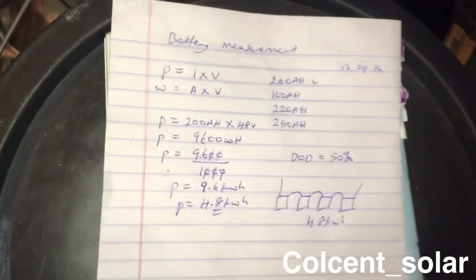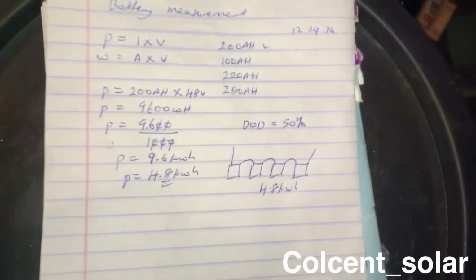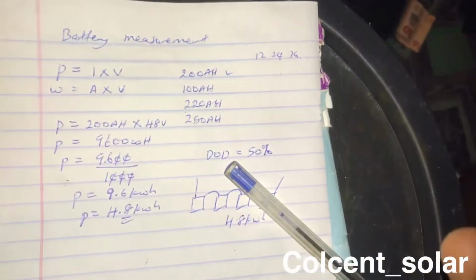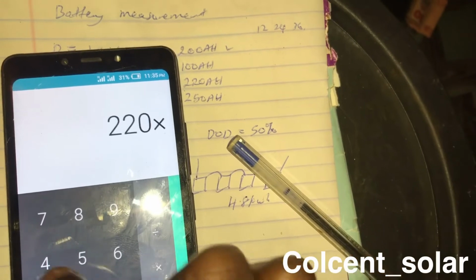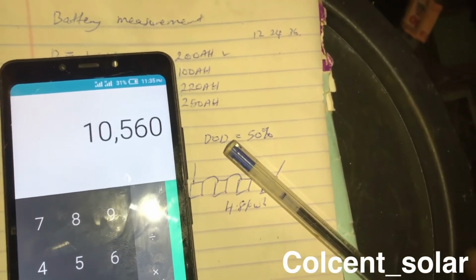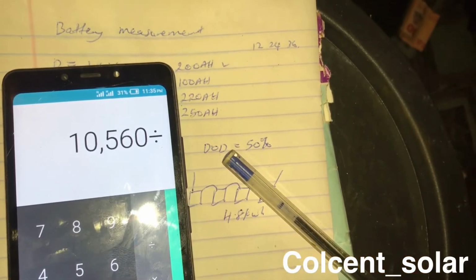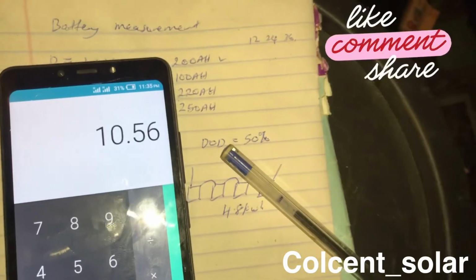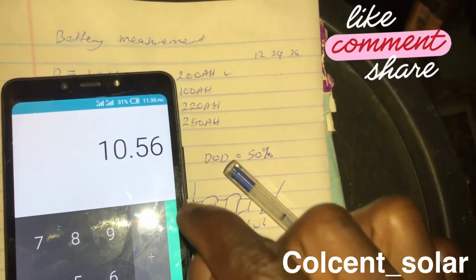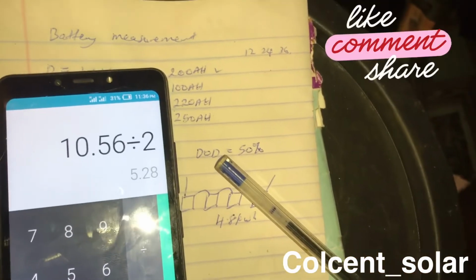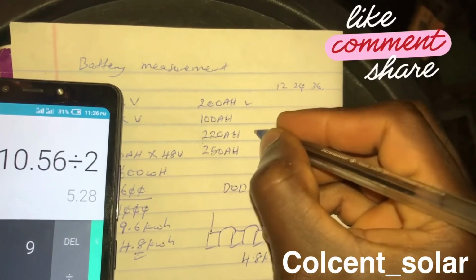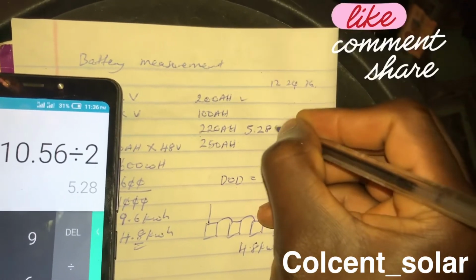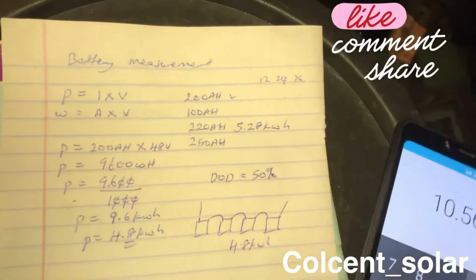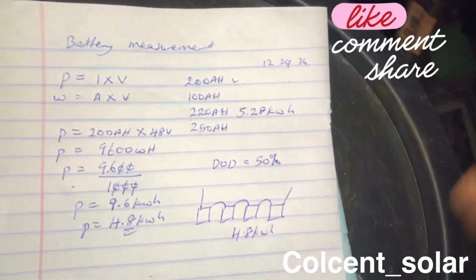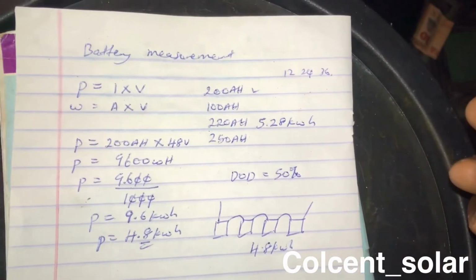So let's just do that really fast. That's calculating with 220 amps. The mathematics is just very simple. So 220 times 48 giving you 10,560, divided by 1000 giving you 10.56 kilowatts. Then you divide it by 2, so having 5.28 kilowatt hour. So this is actually very simple. Very simple. So this is just the way you do it.